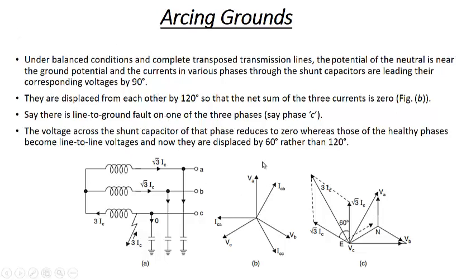So under balanced conditions, this will be our phasor diagram. The voltages are displaced from each other by 120 degrees, and the sum of the three capacitive currents will be equal to 0. Now when a single line to ground fault occurs in one of the phases, let us say phase C, the voltage across the shunt capacitor of that phase reduces to 0, whereas those of the healthy phases become line to line voltage. Now they are displaced by 60 degrees rather than 120 degrees. You can see from here, this is VA, this is VB, they are displaced by 60 degrees. Earlier it was 120 degrees, because they now become line voltages.